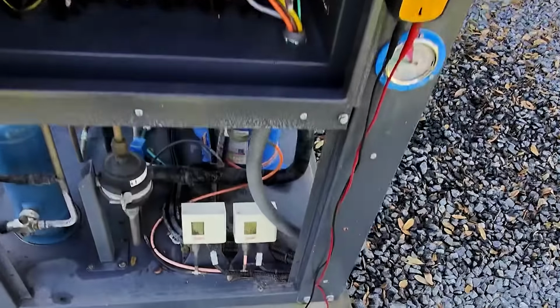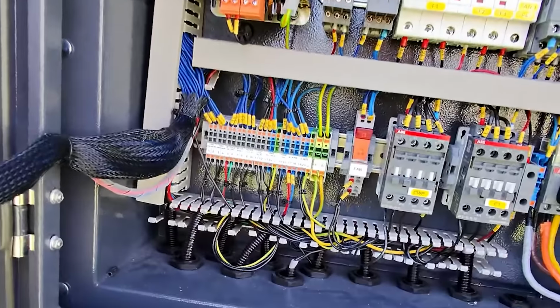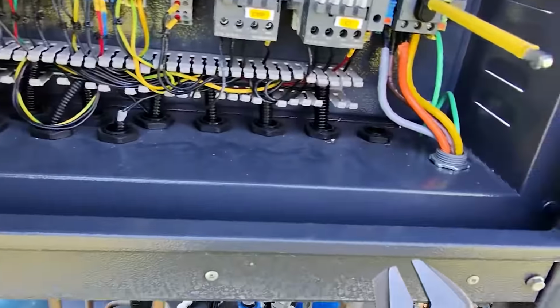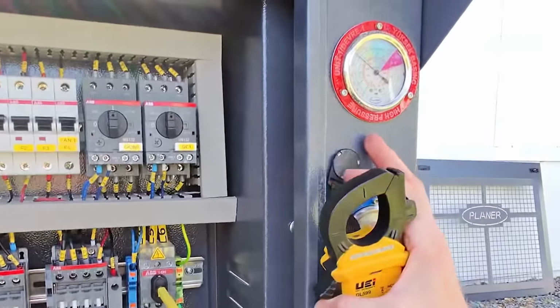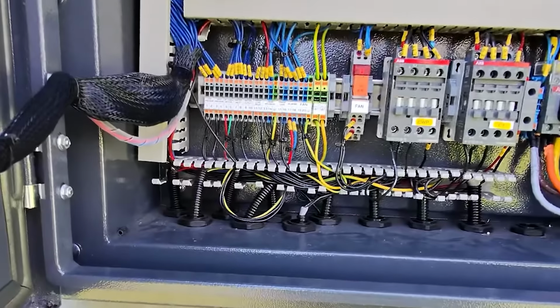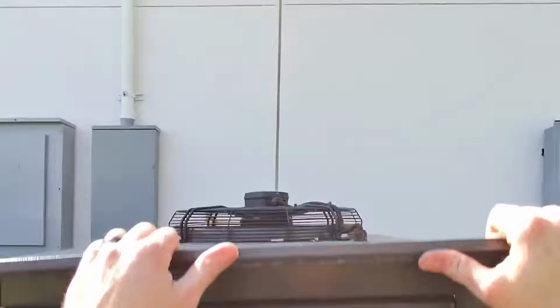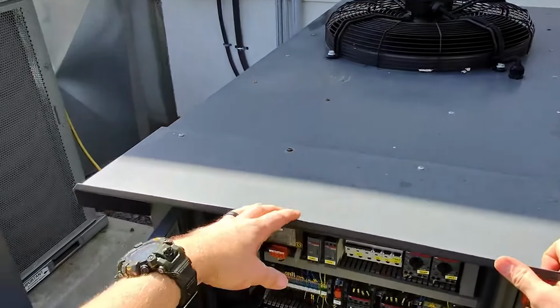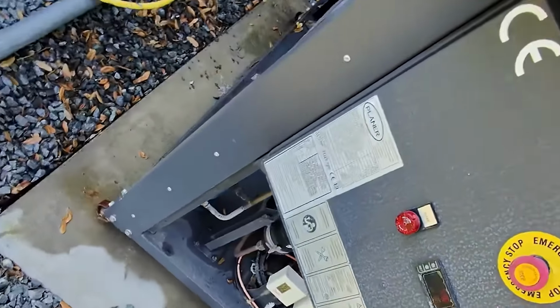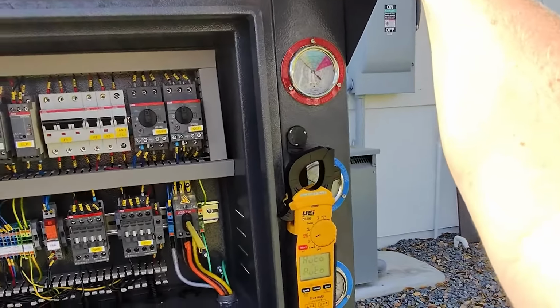So I naturally took my crescent wrench and proceeded to beat it. And I got it to energize again. And now that it has energized, we are in business. So the condenser fan is running, no water pump alarms as we speak right now, and head pressure is staying down.